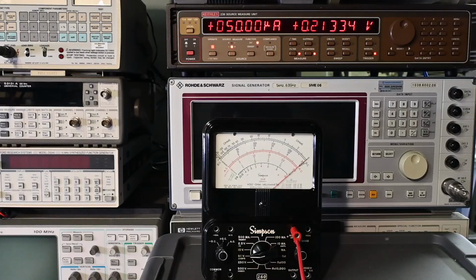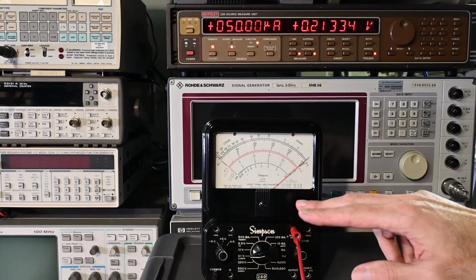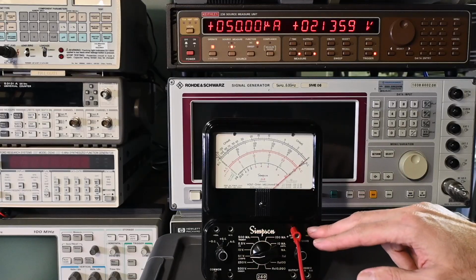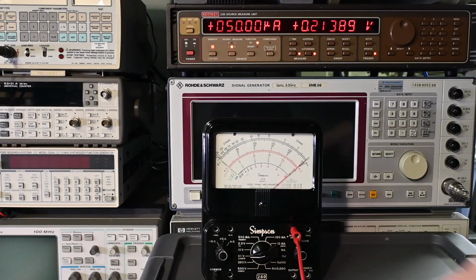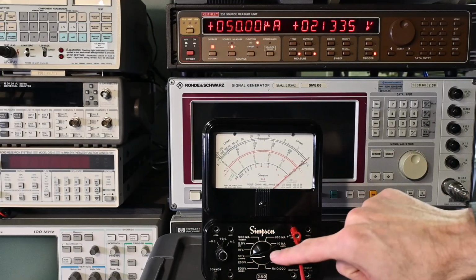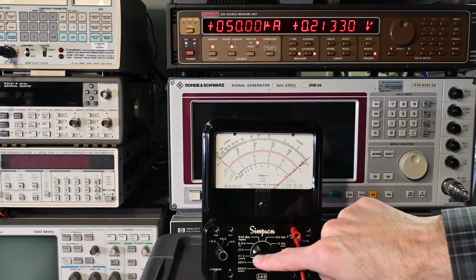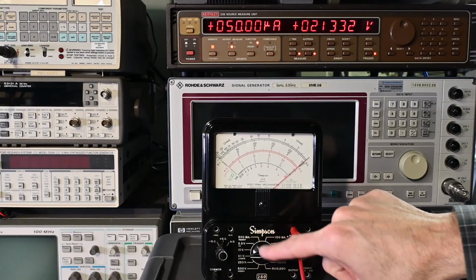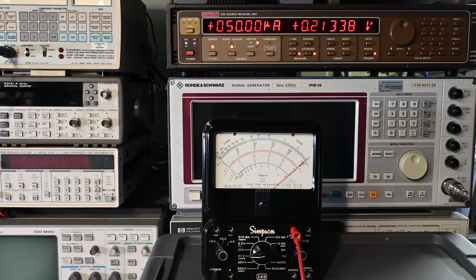All right, for the second DC calibration, the 250 millivolts full scale, I have the test leads connected on the front panel. So the positive is on the 50 microamp and 250 millivolt input. The negative is on the common, and the function switch is on the 50 volt and microamp setting, just to ensure that this isn't in a position that affects the measurements. And this is on the positive DC input.